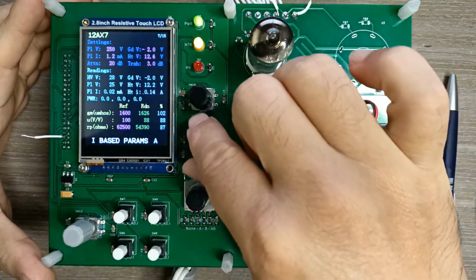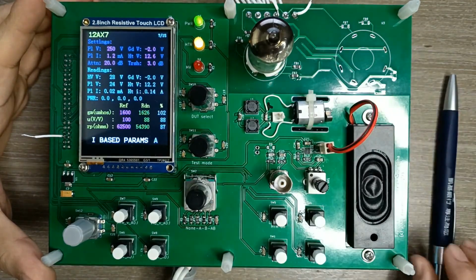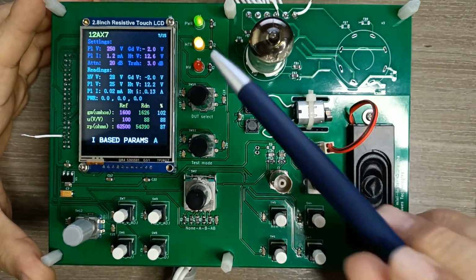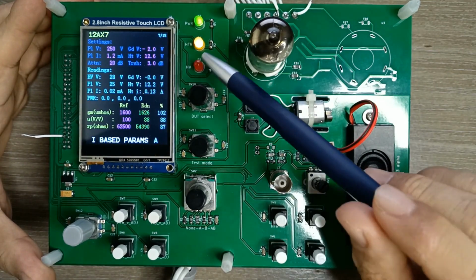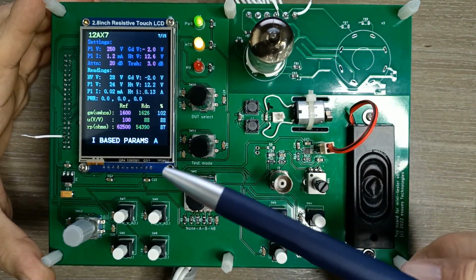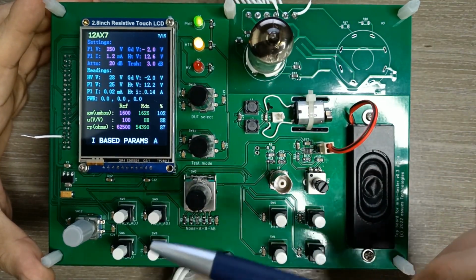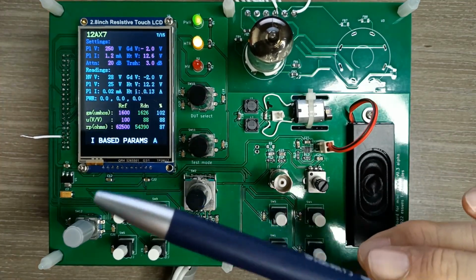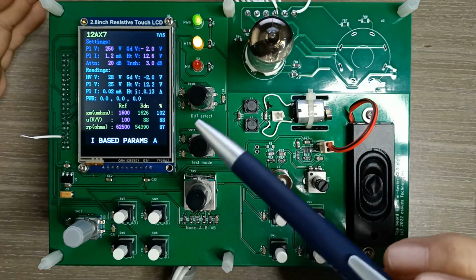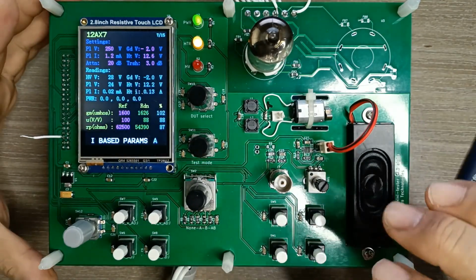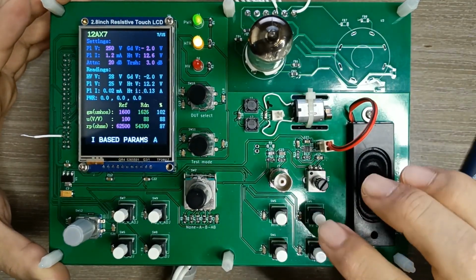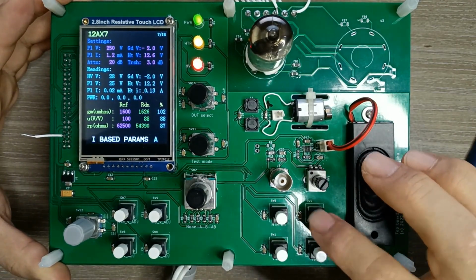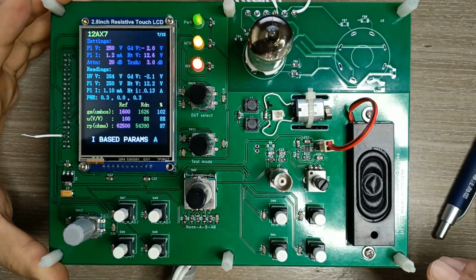So every time we change test mode, you probably notice that the high voltage LED is turned off and the heater supply remains on, because between different test modes we might want to change the high voltage setting. As a precaution, the machine always switches off the high voltage supply, so we need to turn on the high voltage supply manually.